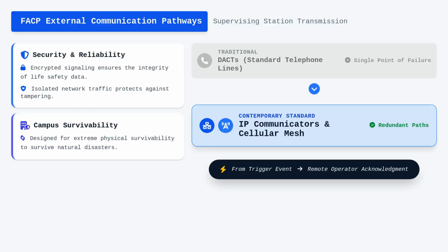Communication to the outside world is equally vital, as the FACP must reliably transmit event data to a supervising station through diverse pathways. Digital Alarm Communicator Transmitters, or DACTs, have traditionally relied on standard telephone lines, but contemporary standards demand more robust and redundant transmission technologies. Today, IP communicators and cellular mesh networks are standard, providing multiple paths that bypass the single points of failure inherent in older copper line systems.